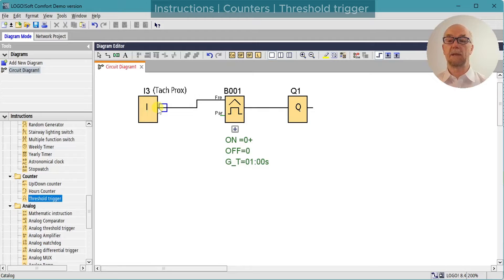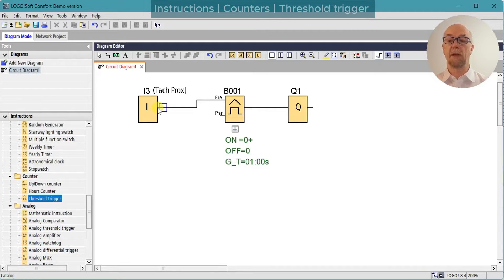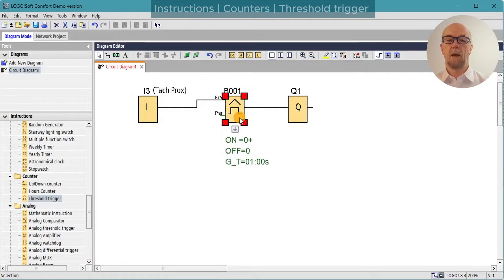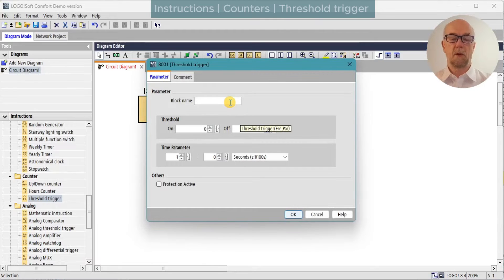The input must not be connected via another function block such as logic gates. Maximum frequency is typically 5 kilohertz for the high-speed inputs, but as low as 4 hertz for regular inputs or for an input to the threshold trigger from another function block. Check the manual for the model you're using. We'll document as normal.